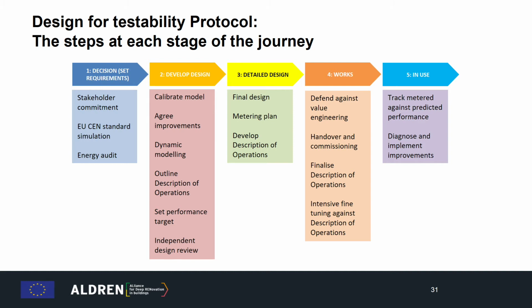This is something we found really important in making sure the design is fit for purpose. The detailed design has to include generating a validation plan and making sure the metering is in the right place. Once the works start, defend against value engineering, carry out very careful handover and commissioning, and don't forget intensive fine-tuning once the building starts operation. Then, in use, track the actual performance against predicted performance, making sure any deviations between design and prediction are dealt with by remedial measures.